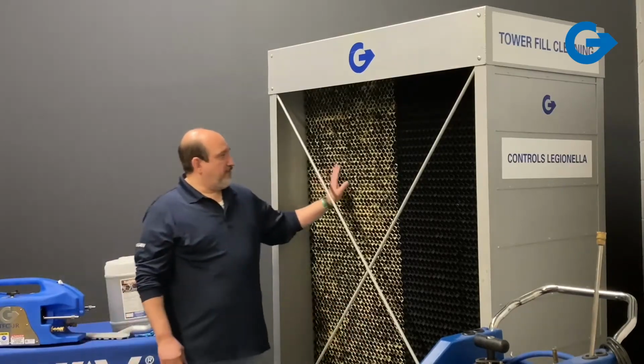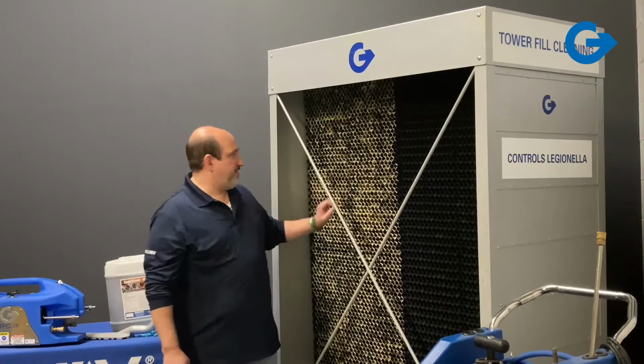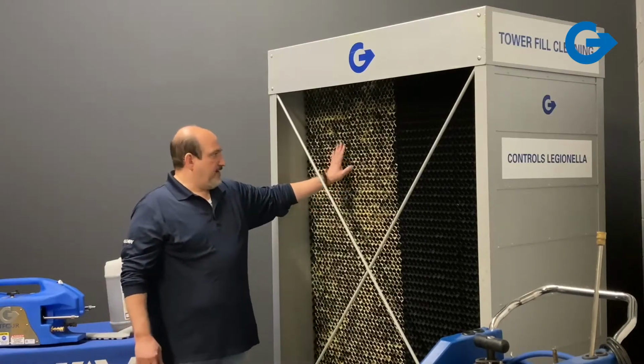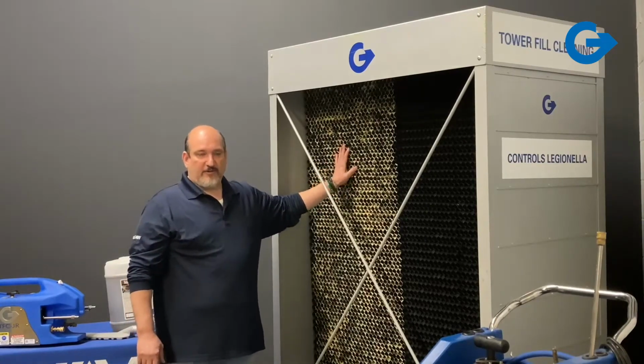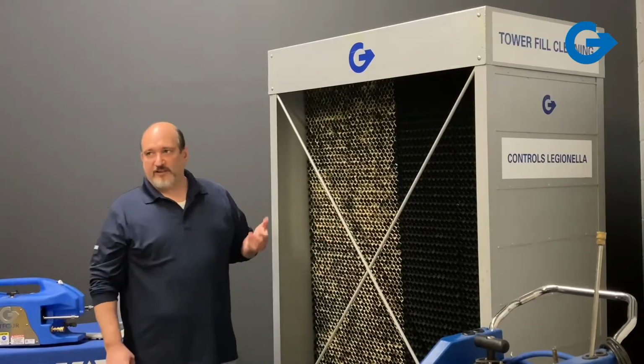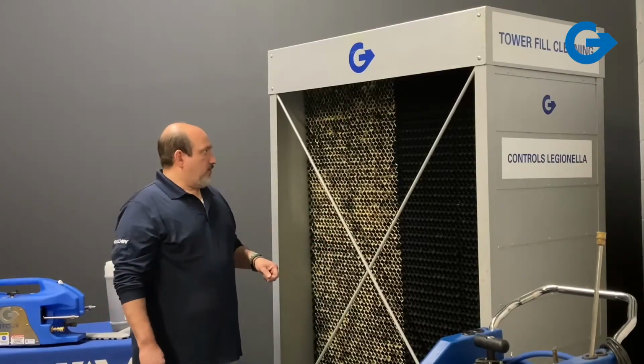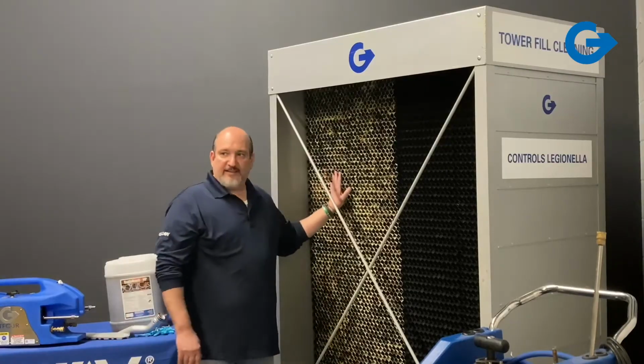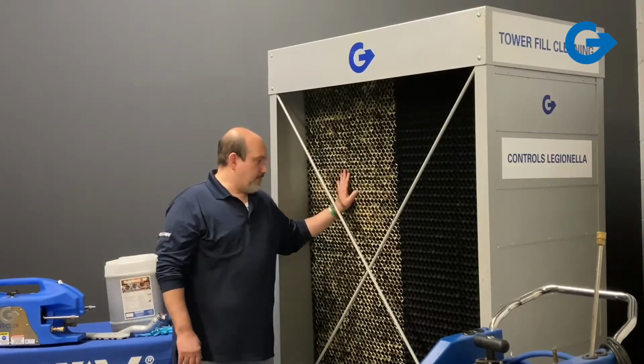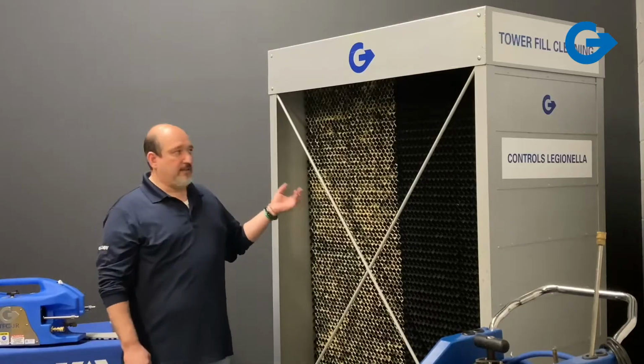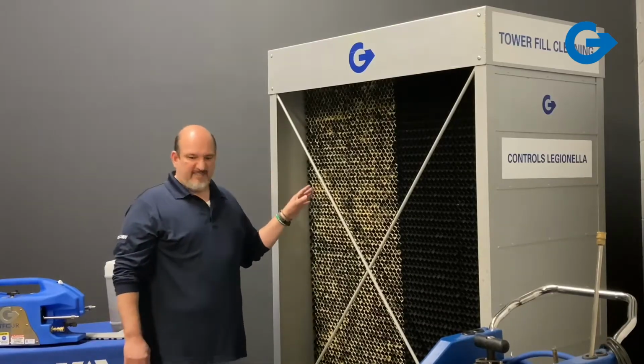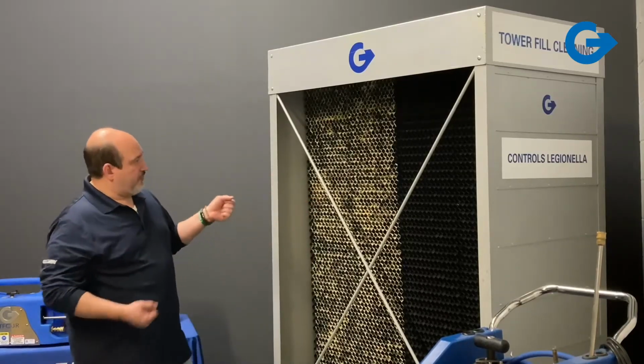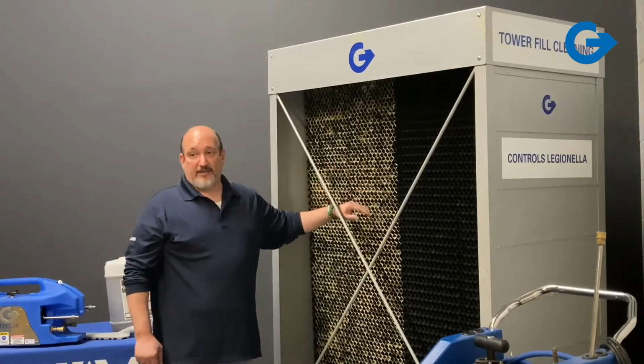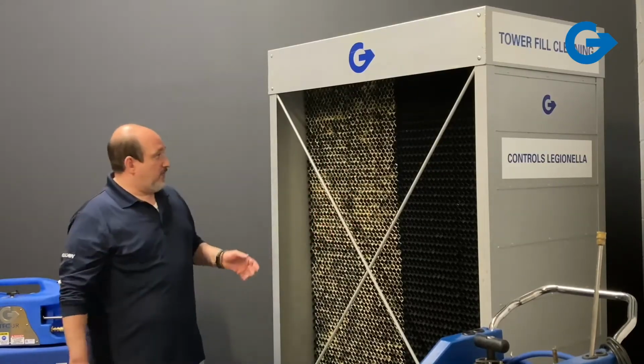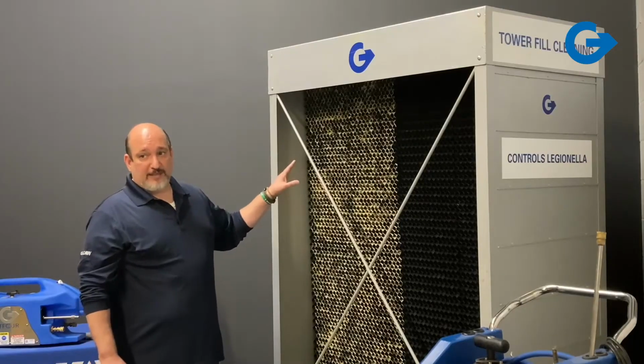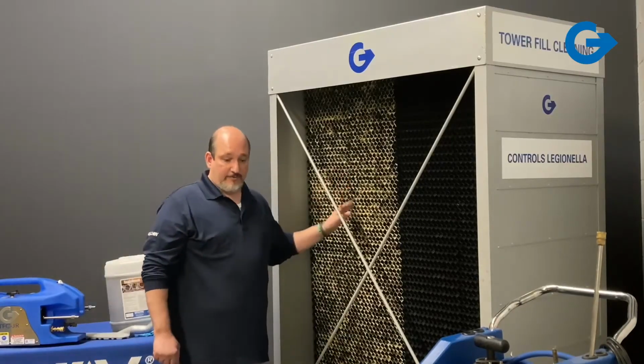What's happening to the fill, as you can see in this depiction, is you get scale that can collect on it. The scale is just mineral deposits left behind from the water. A lot of times it's pretty difficult to clean scale off a fill, because it adheres very well, and the fill is also pretty delicate. If you take a pressure washer and get too close, it's going to cut a big swath in the fill, and we don't want to do that. So we wanted something that lets you clean the fill without damaging it, while also getting that scale off.